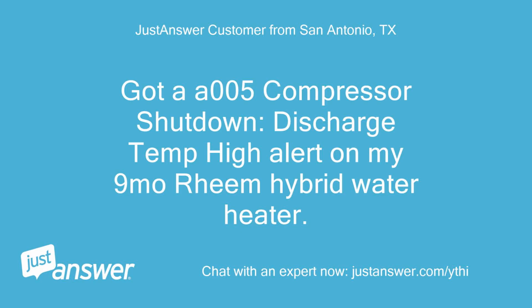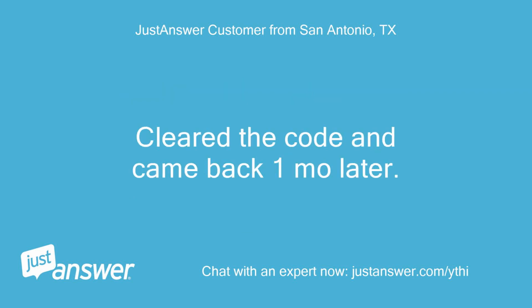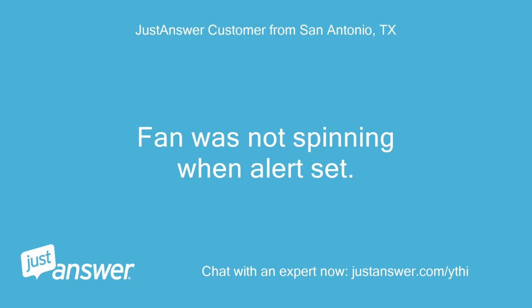Got a a005 compressor shutdown, discharge temp high alert on my 9 mo Rheem hybrid water heater. Cleared the code and came back 1 mo later. Fan was not spinning when alert set.